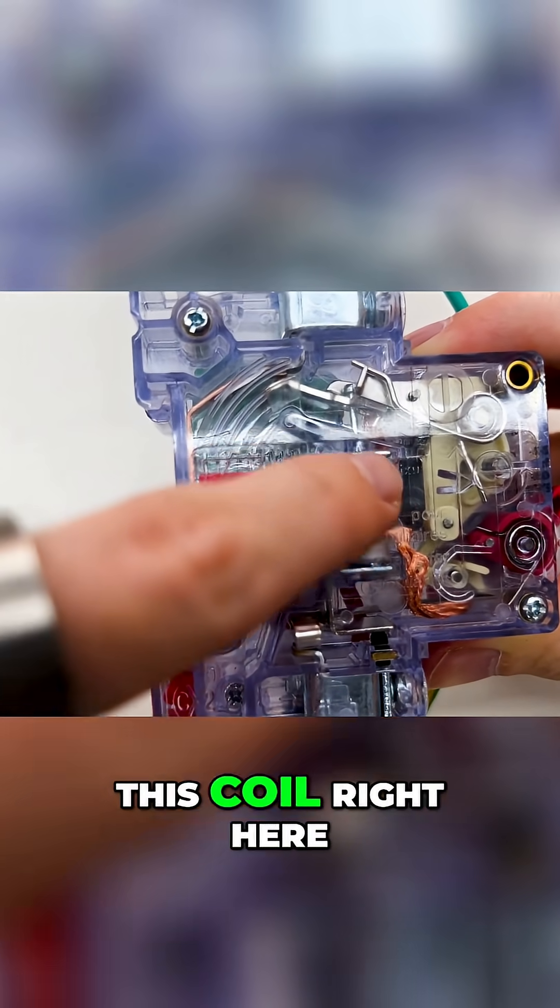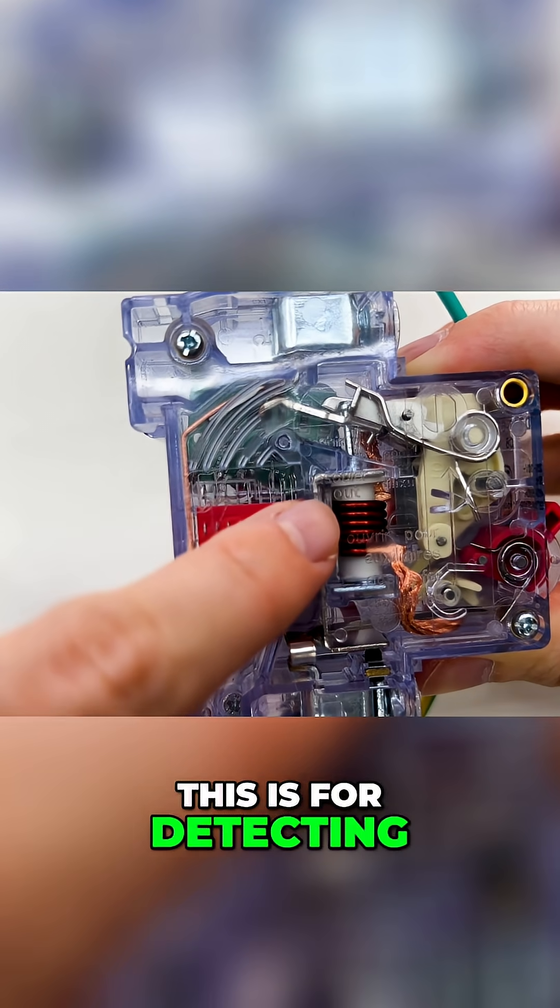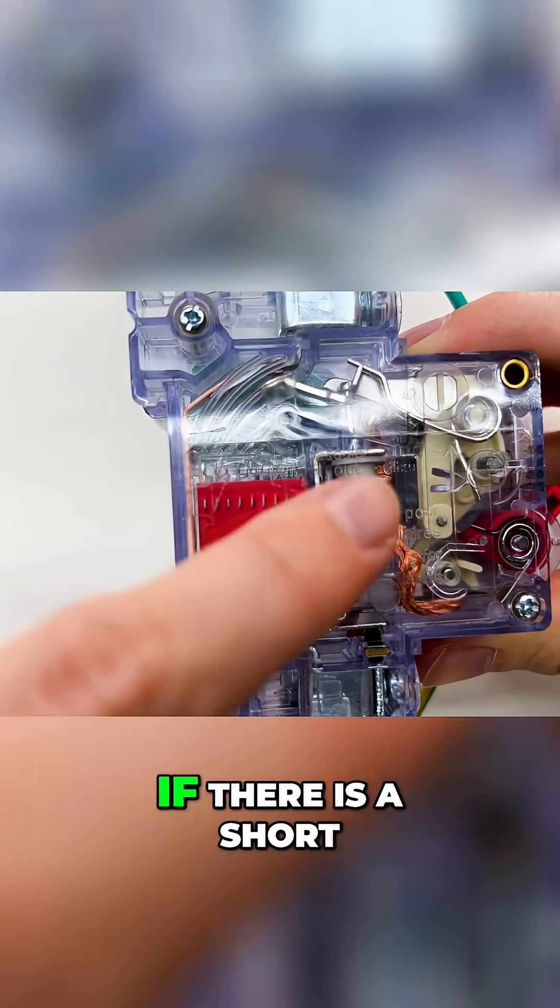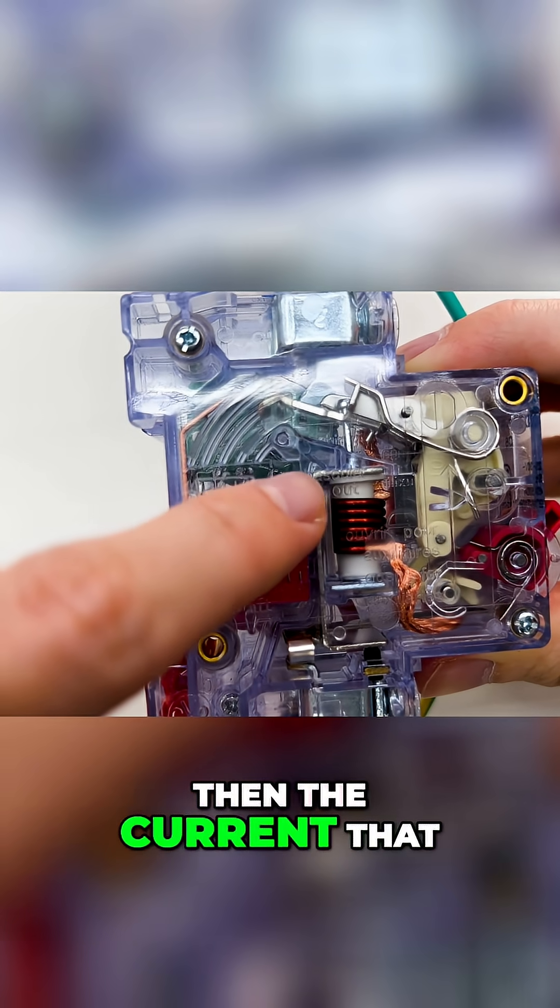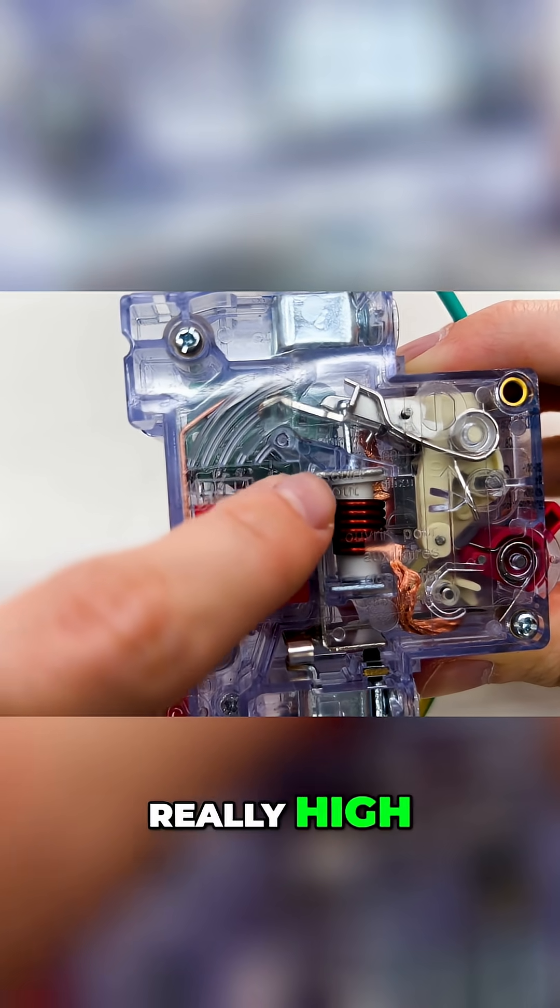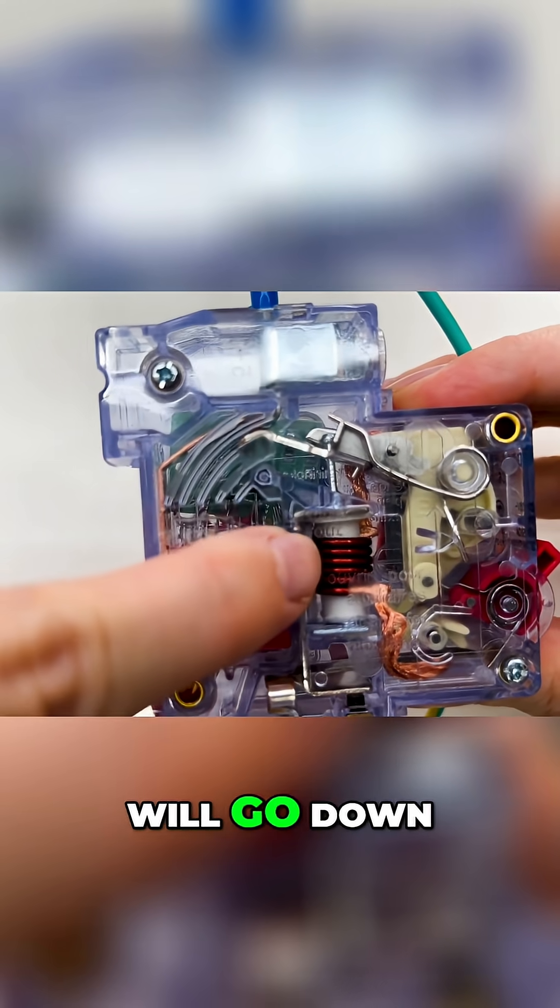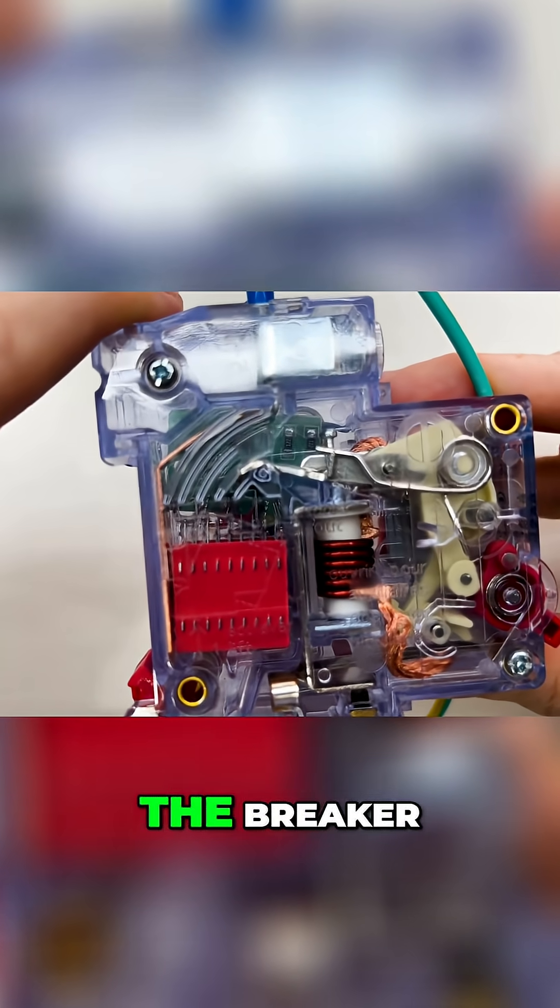But the second thing is this coil right here. This is for detecting short circuits. If there is a short, the current that will flow will be really high. This pin right here will go down and it will disable the breaker.